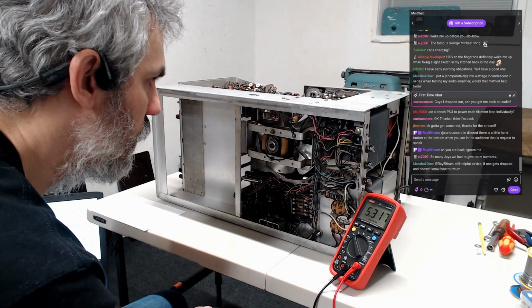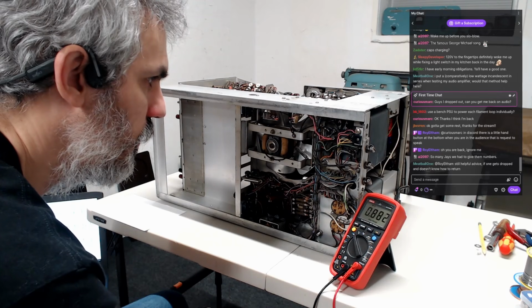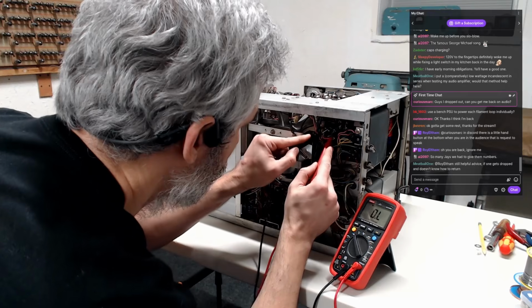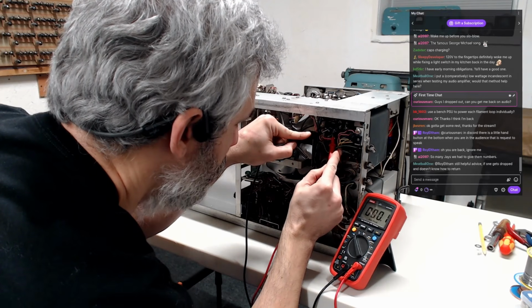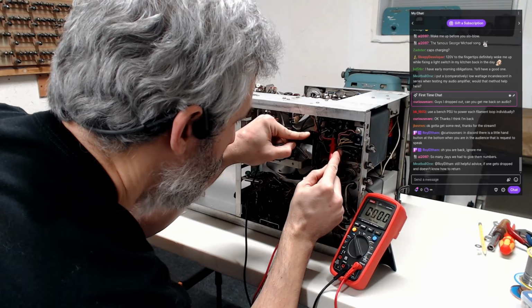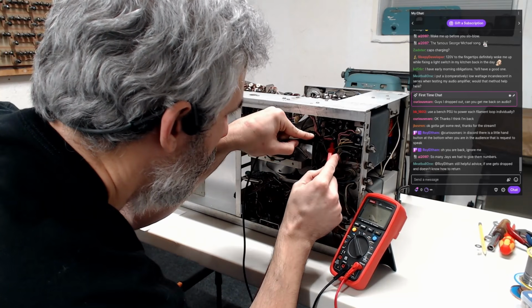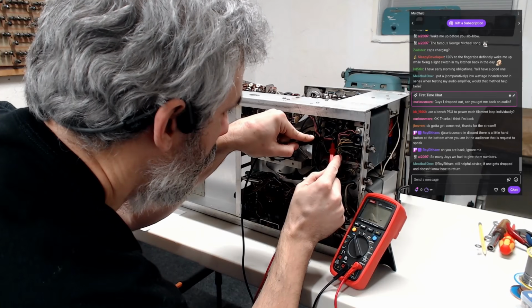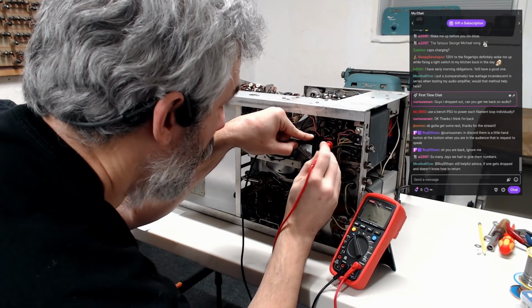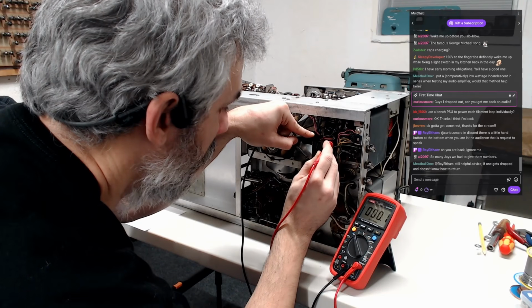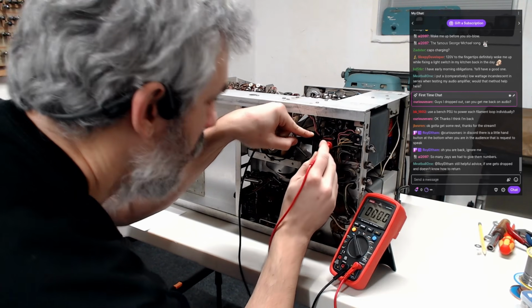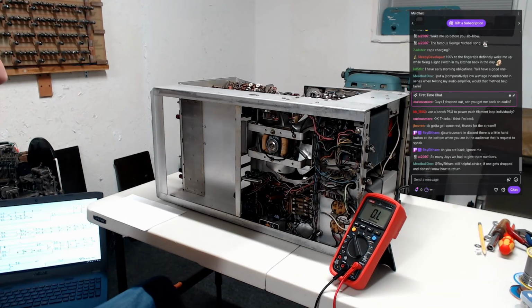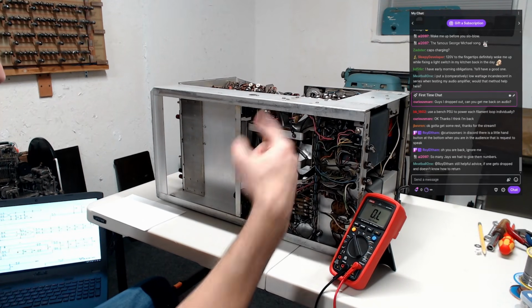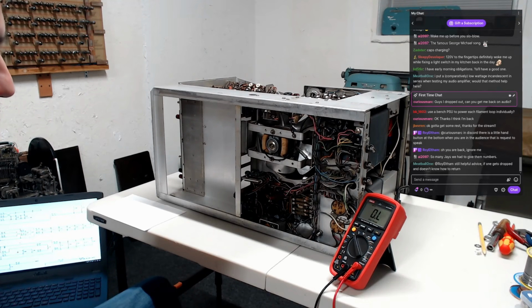Do you have another 6.3 winding that you could check the resistance from? Yeah, I can check this one up here. That one says 0.1 ohms. 0.0 ohms. So it's normal, I don't know if that's normal, but that's what we're seeing. Copper, 0.1, 0.0. Yeah, I think it's just like we're seeing the winding of the transformer comes out at 0.0 because it's such a high current, low voltage winding. So it's going to be thick wire with not that many turns, right?